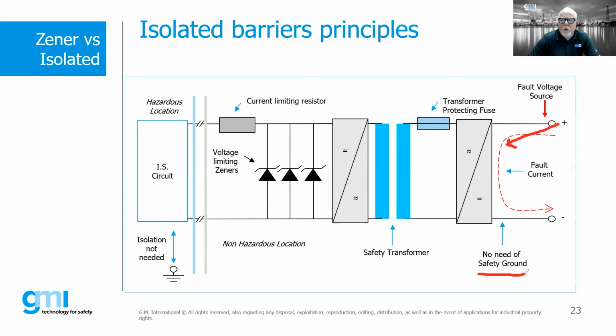Now, there may be a ground that we have for barriers in general - like any electrical component, we may want to ground the DIN rail that the galvanically isolated barriers are mounted to. But we're not having to actually have a dedicated, intrinsically safe, clean earth. That's really the huge benefit you find with a galvanically isolated barrier versus a Zener diode type barrier - that's the main difference.